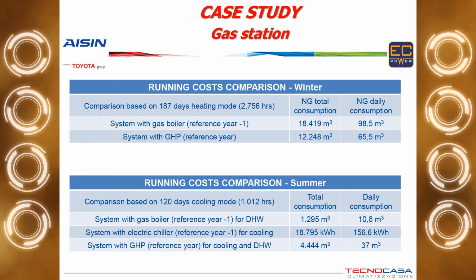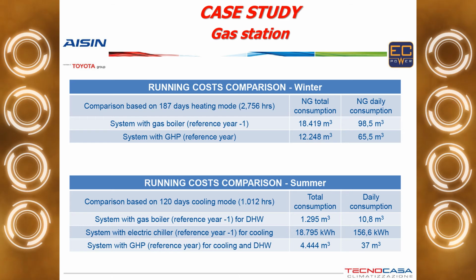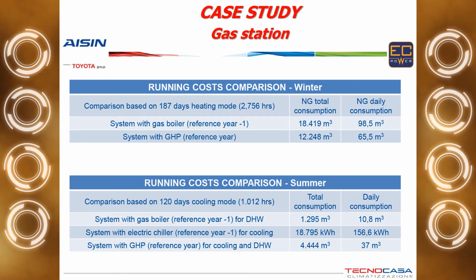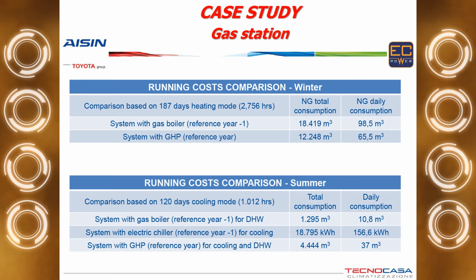Of course, we also wanted to compare what was going on in summer, because we sold the unit to the customer, saying that he could spare the electrical cost of the chiller throughout the winter, because of course if you have a 50 kilowatt, 100 kilowatt chiller, I mean electrical consumption, you have to pay the amount the whole year, even though you use the chiller only 3 months maybe. So in this case we made a comparison based on 120 days of cooling mode, almost 1,000 hours.